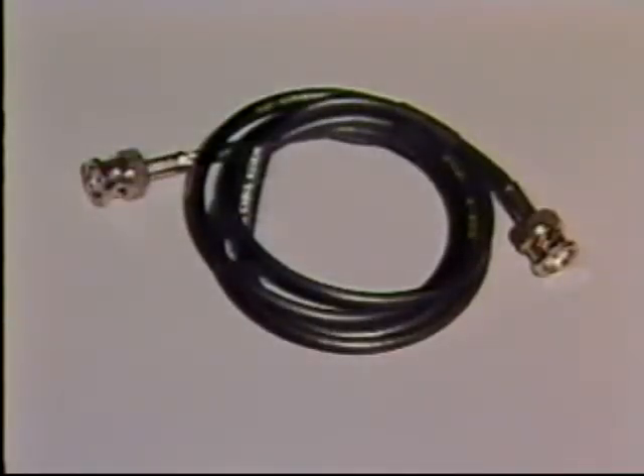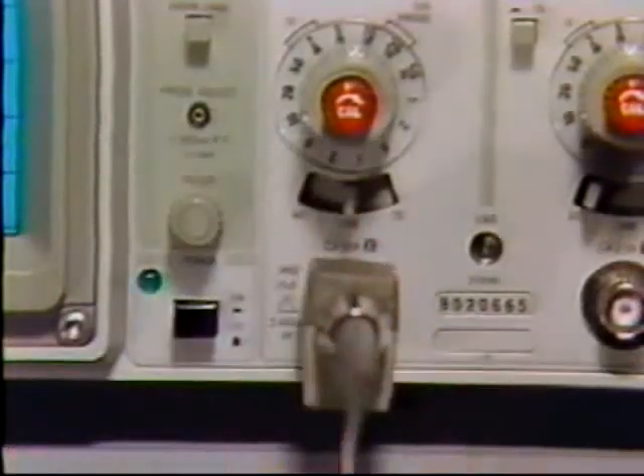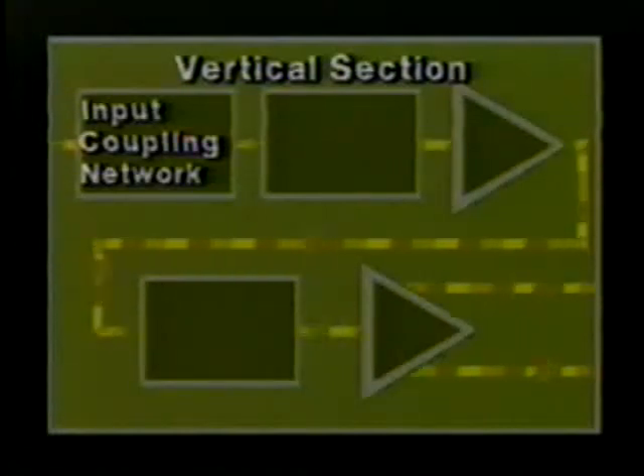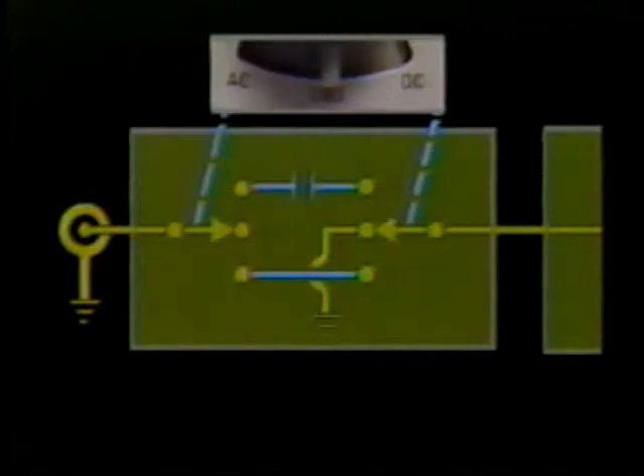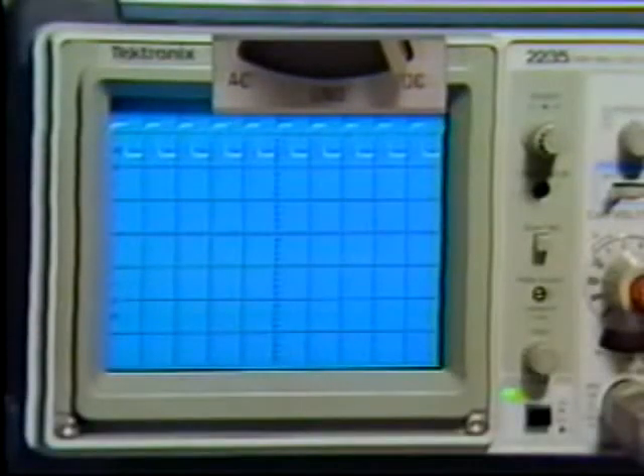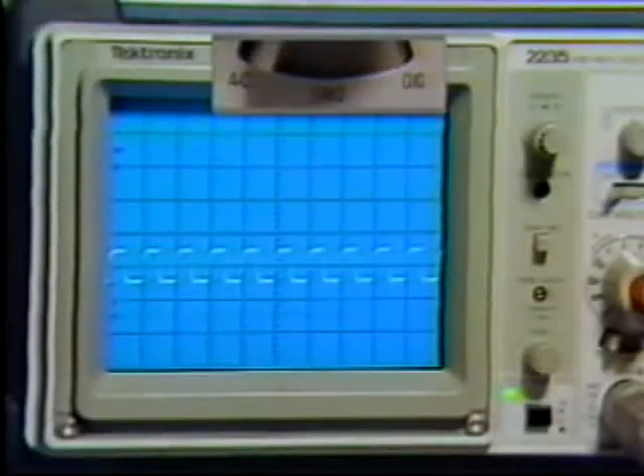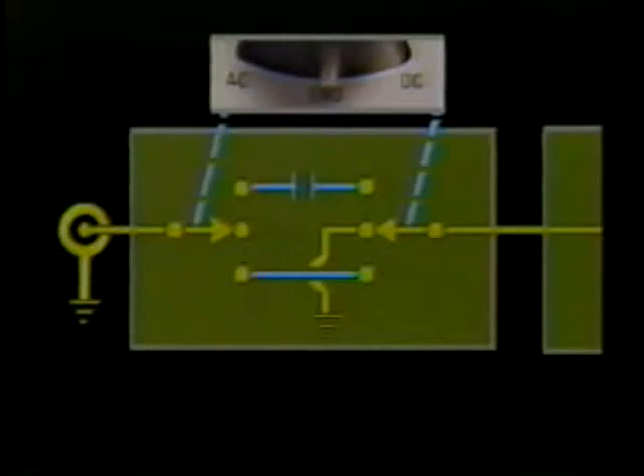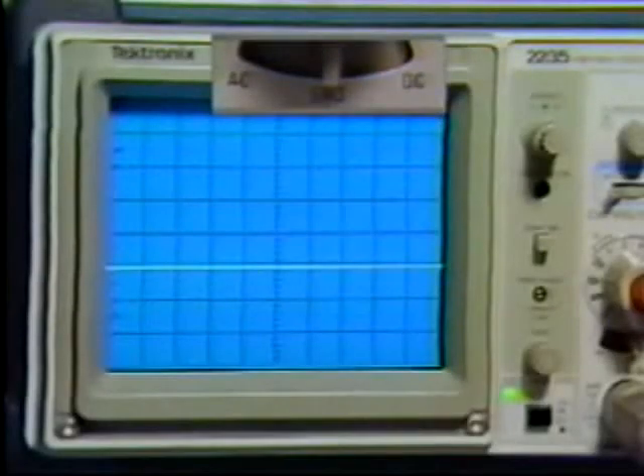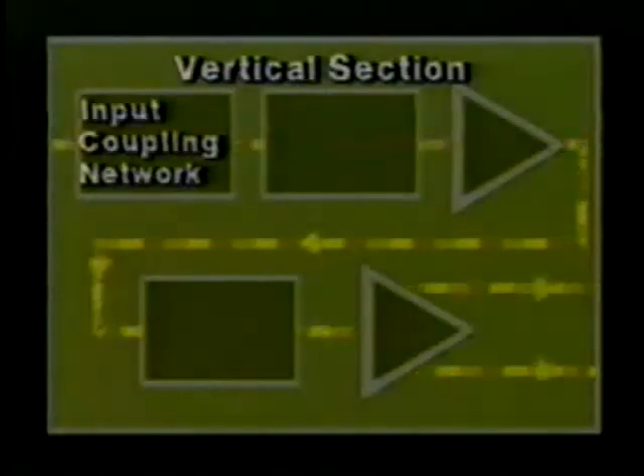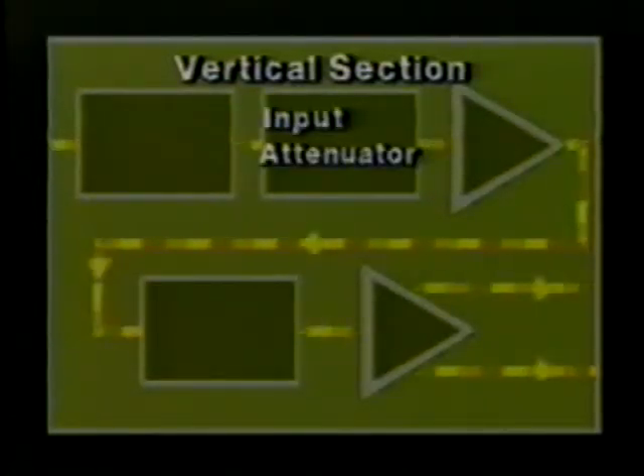After a signal source is connected to the vertical input BNC, the signal flows to the vertical input coupling network. The coupling network allows selection of either DC, AC, or ground coupling. DC provides a direct path to the vertical amplifier, coupling both AC and DC components of the applied signal. AC blocks the DC component by inserting a capacitor in series with the input. The ground position disconnects the signal and shorts only the attenuator input to ground — it does not short the applied signal to ground.